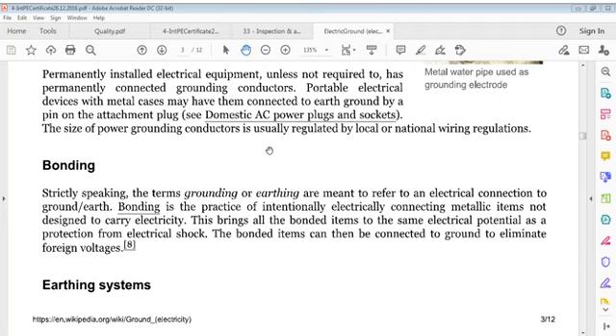Strictly speaking, the terms grounding or earthing are meant to refer to an electrical connection to ground or earth. This means we have to connect electrical connections to ground or earth for the purpose of grounding or earthing. Now, bonding is the practice of intentionally electrically connecting metallic items not designed to carry electricity. This brings all bonded items to the same electrical potential as protection from electrical shock. Bonded items can then be connected to ground to eliminate foreign voltage.